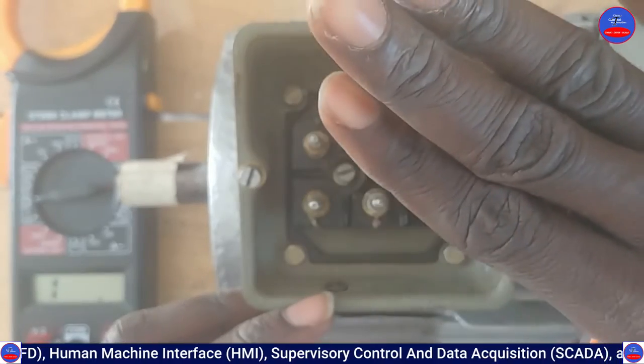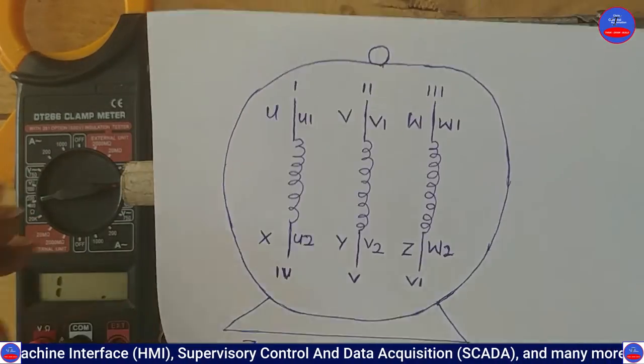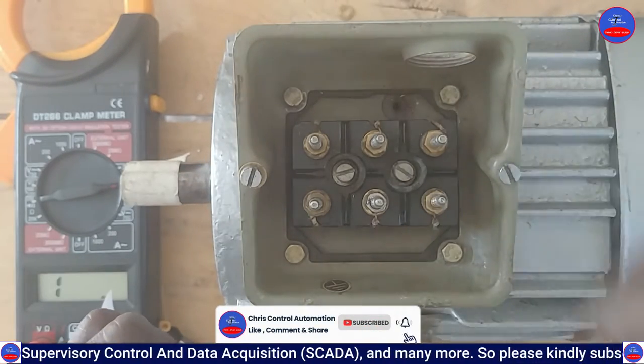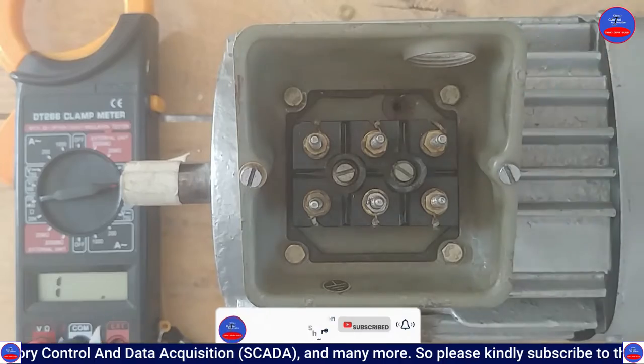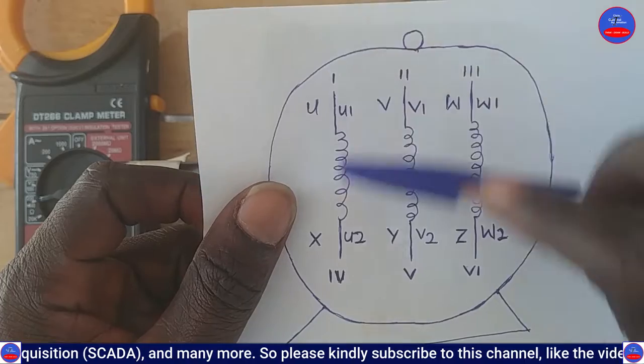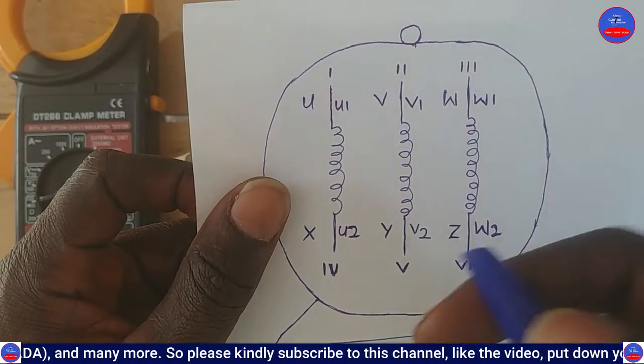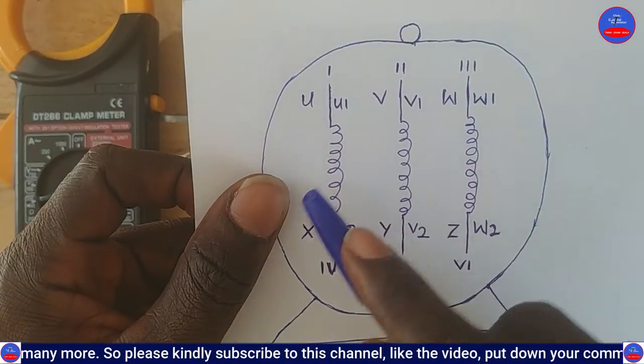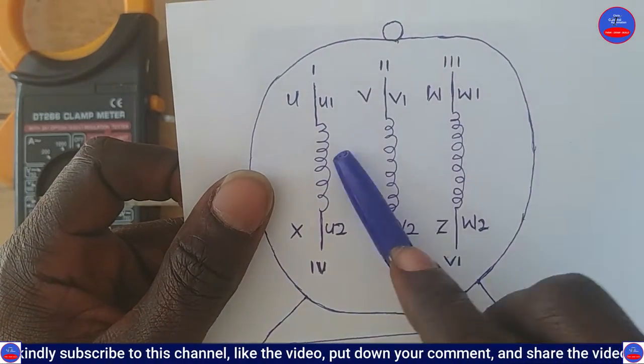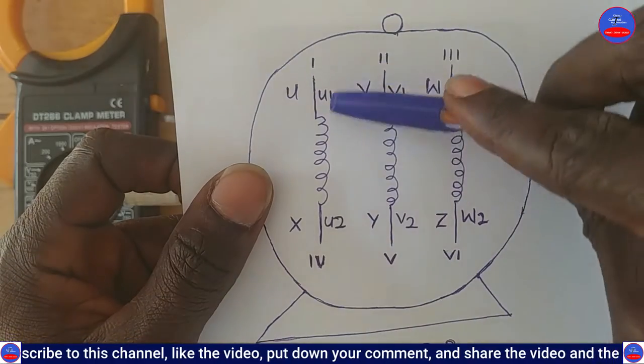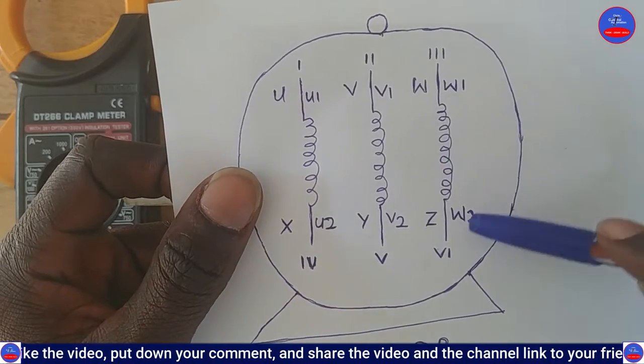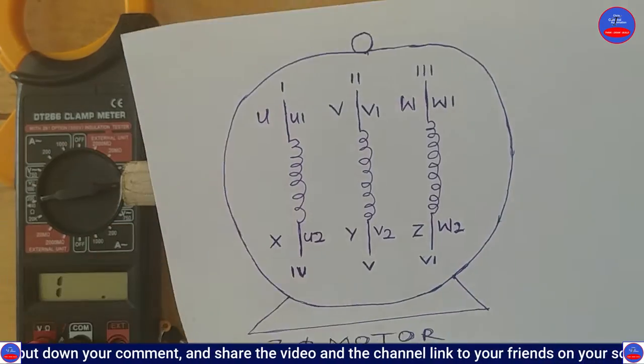Now we are going to identify the windings and test for continuity to know the winding continuity. We have U1 and U2. When we use the instrument to test, if there is no break you should get a reading between U1 and U2. The same applies to all of them. So we will test for U1 and U2, then V1 and V2, then W1 and W2. Now let's use the instrument to test.